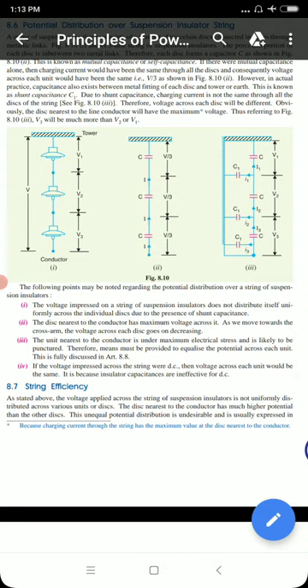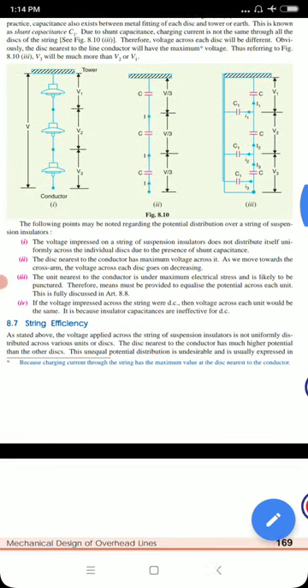Because the nearest insulator to the conductor has the most electrical stress, it is most likely to be punctured. Therefore, means must be provided to equalize the potential across each unit — we will see this in the next classes. If the voltage were DC, the voltage across each unit would be the same, because shunt capacitance is ineffective for DC systems. The unequal voltage distribution occurs only due to AC.